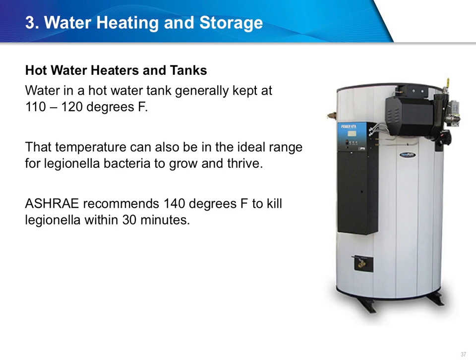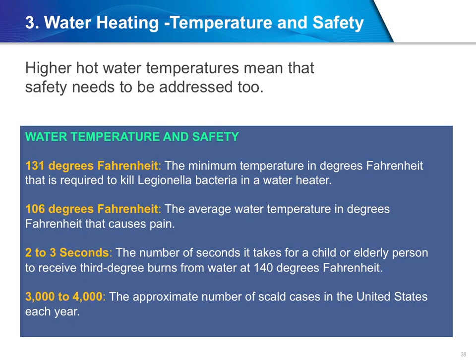Constant movement in tanks can reduce the growth of scale and thus help mitigate Legionella growth. There are also tankless options that can be considered. While heating water to the rapid kill range is one of the most effective and reliable control measures for dealing with Legionella, it is not necessarily the best temperature for water to be used by people. On average, any water that is above 106 degrees Fahrenheit will cause scalding and pain in humans, while water that is 140 degrees Fahrenheit can cause third-degree burns in a matter of seconds.